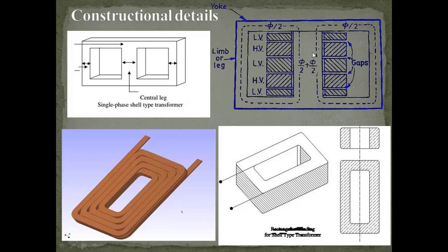Both the HV and LV windings are wound on the central limb in shell type transformer, and it is sandwich type — meaning HV and LV are alternatively placed. This is the cut section elevation of a single phase shell type transformer. We have three alternate LV and HV layers, and between the windings there are gaps for insulation, including a gap between the windings and the limb.